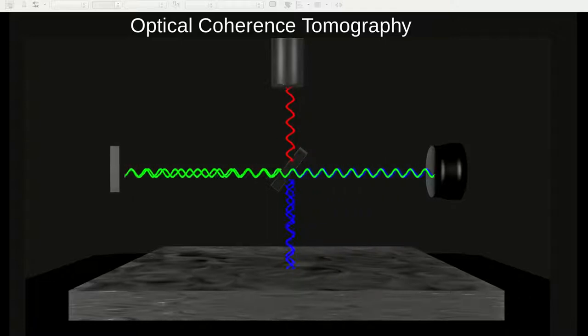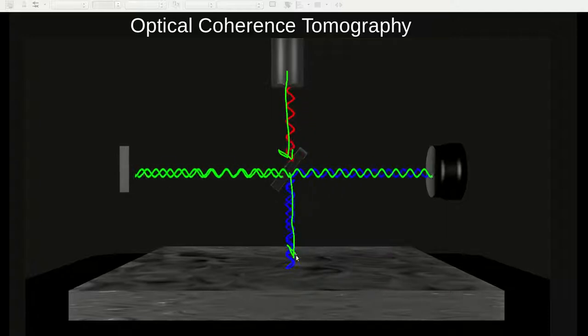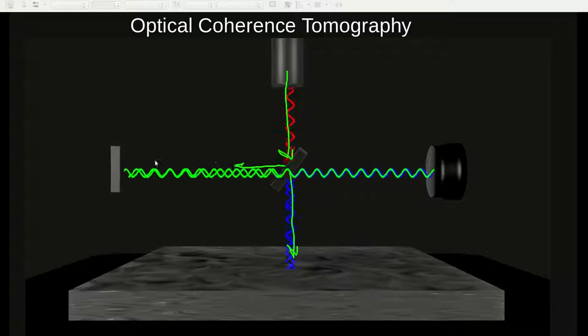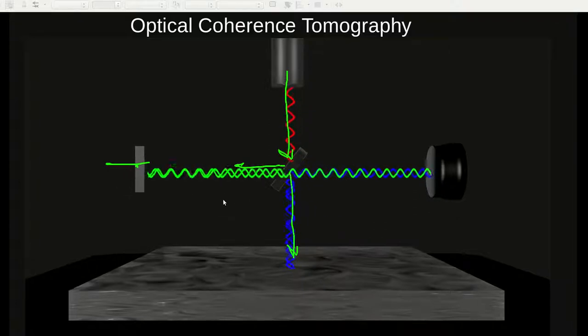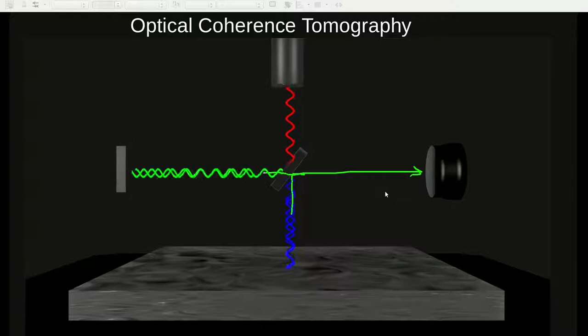The following video shows an example of a Michelson interferometer for a monochromatic radiation source. The radiation emanating from the source goes to a beam splitter. At the beam splitter, part of the radiation is transmitted down to the substrate being measured and part is reflected to a movable mirror. The radiation then is recombined from the substrate and the mirror and is sent to a detector. The detector measures the temporal interference pattern of the radiation.